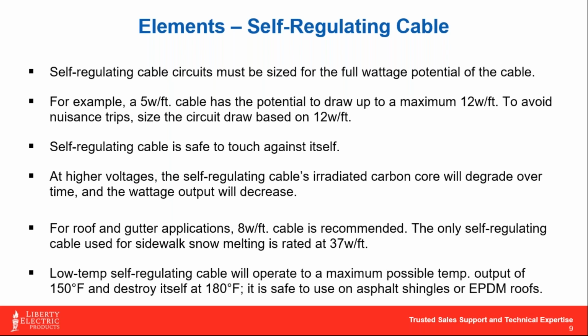Now, for folks that have had any experience with this cable before, I'm just going to point out a nice rule of thumb. When you're running power from a supply panel to a junction box, and you want to come out of that junction box with heat cable along your roof or along a pipe, it's not the power run that counts footage towards your circuit maximum length. Okay, so if you had to run 100 feet of standard pipe and wire, and you've got a number 10 inside of that conduit feeding power, you don't count that 100 foot of power wire. You're just counting feet of heat cable on the circuit before you get to your maximum circuit length.